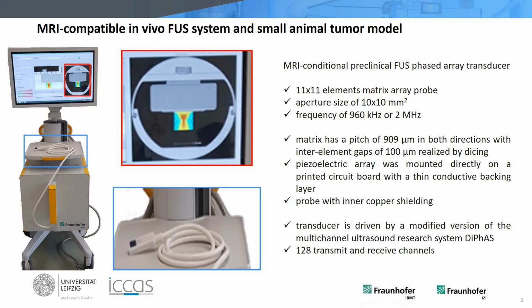Here you see the whole system for MRI-guided FUS in small animals. The probe consists of an 11 by 11 element matrix array working at a frequency of around 1 MHz, or another transducer with 2 MHz. For MRI compatibility, the probe has an inner copper shielding. On the screenshot, you see the software for the treatment planning, using the sound field inside of a preclinical MRI animal bed.